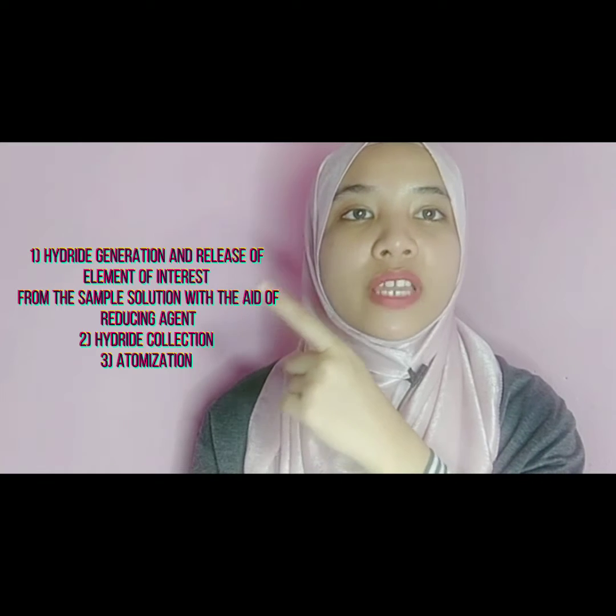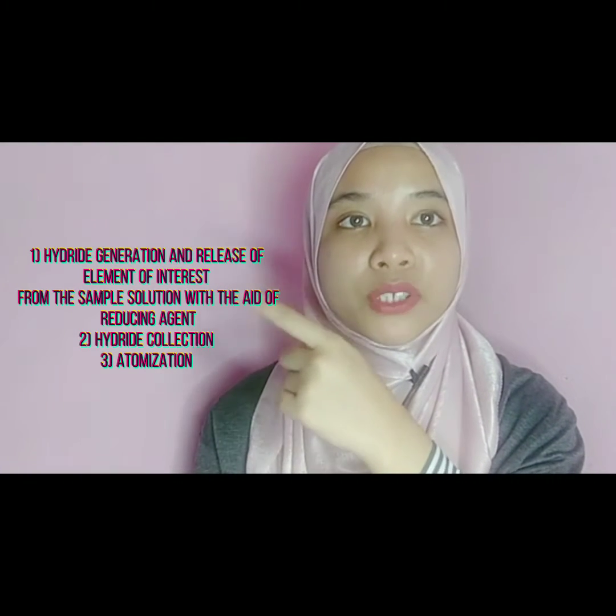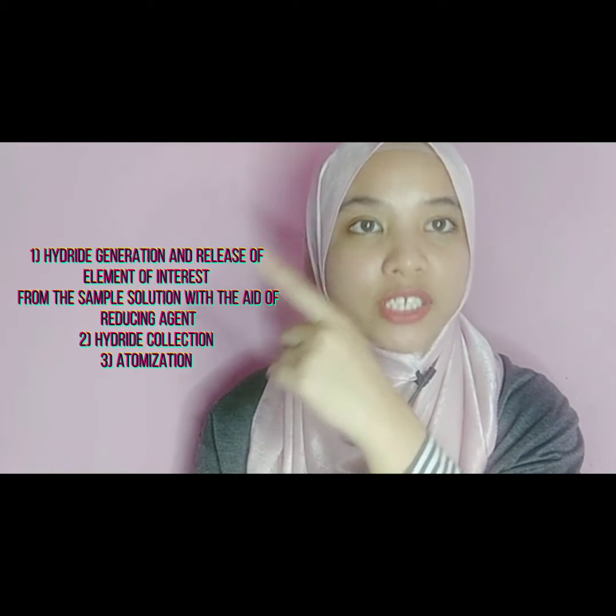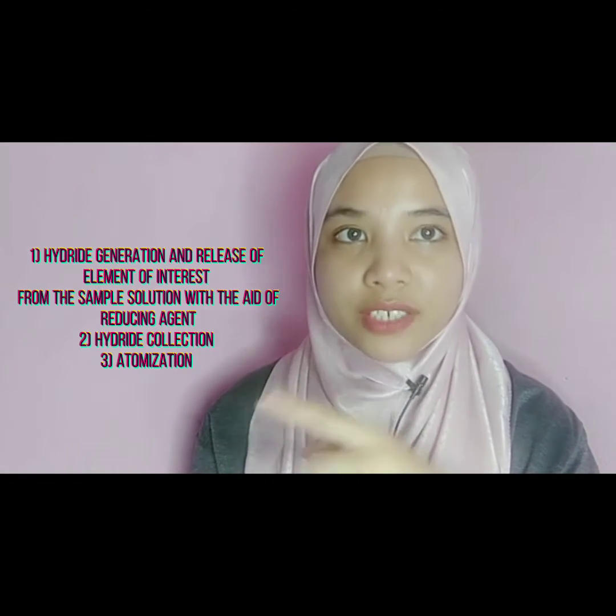The sensitivity of this technique is due to its ability to determine the trace levels of metals at wavelengths below 200 nanometer, a region considerable with spectral interference of radicals in conventional flame AAS. Hydride generation technique involves three processes, which are the hydride generation and the release of the element of interest from the sample solution with the aid of a reducing agent. Secondly is the hydride collection, and the third one is atomization.